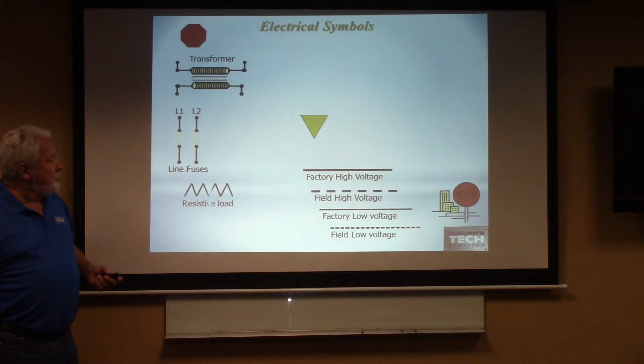When you see a load drawn like this, it's going to be a resistive load. That's going to tell you that it's going to produce heat. That's a heat strip. That's a crankcase heater. You're going to see that. When it's drawn with the points on it, it's going to be heat. When you see it drawn with the loops on it like this, that's going to be an inductive load. That's going to be a magnet of some sort. Does that make sense to you? It might be a contactor coil. It might be a fan relay coil. It may be a coil on a blower motor. Something that's going to produce magnetism. So we have resistive loads and inductive loads in there.